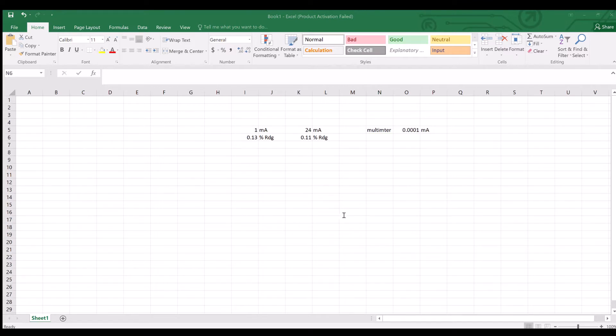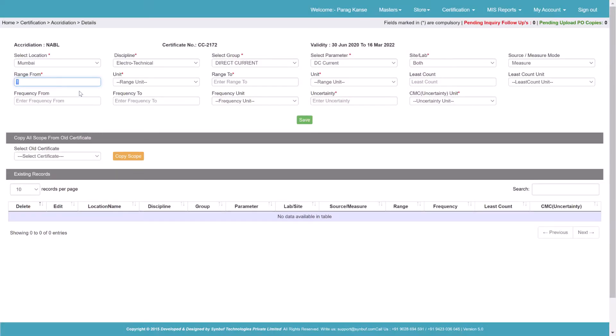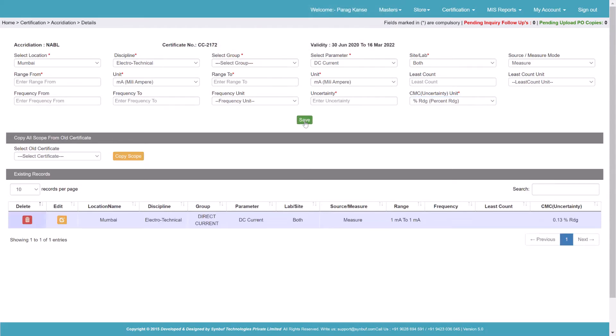So how will I enter this entry in our application? Here we'll enter 1 milliampere to 1 milliampere. Least count we'll keep blank as it is not applicable in this case. Frequency is not applicable, we'll leave it. Uncertainty is 0.13% as RDG. I will select these and save it. Then I will add one more entry for the same parameter and same range.